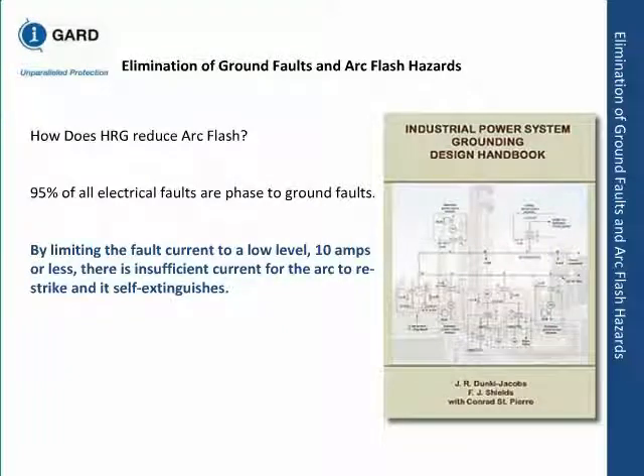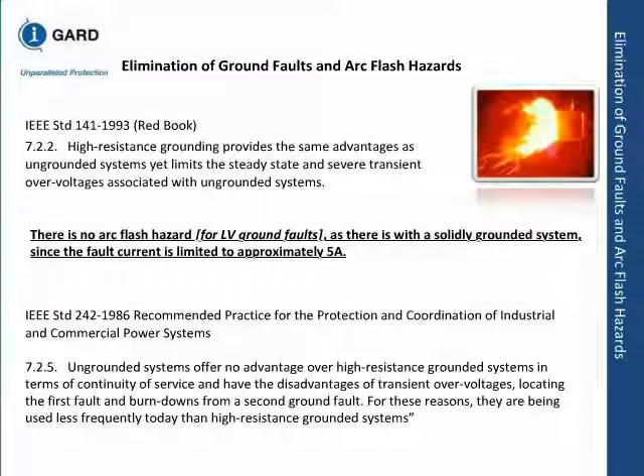This is a reference from IEEE Standard 141, commonly called the Red Book. They tell you the same thing. High-resistance grounding has the same advantage as an ungrounded system, in the sense that the first ground fault would not interrupt you. That was the primary reason for the delta system being ungrounded. But the advantage is that you don't have the transient currents and overvoltage associated with an ungrounded system. Others, see the highlighted part under it. There is no arc flash hazard in a high-resistance grounding system as there is in a solid grounded system, since the fault current is limited to approximately 5 amps. Now keep that in mind. Later on we'll see this is only true for the first ground fault.